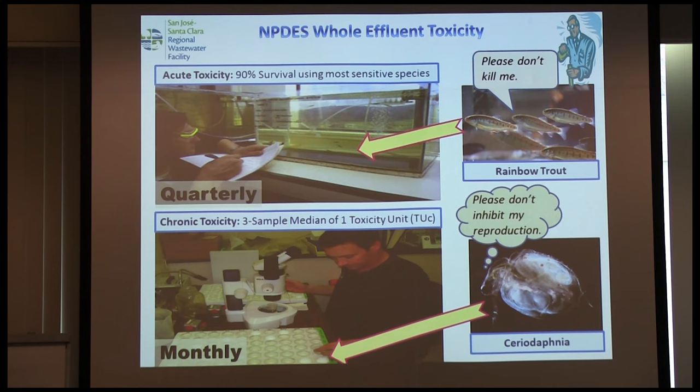The inspector often wants to go see the laboratory area where toxicity testing is done. We use a contract laboratory, bringing in larval rainbow trout — they have to be cultured. More often than not the lab is empty, but on the week of the test they bring in a shipment, put them in test tanks, controlling water, pH, and conductivity. Those fish swim in effluent for about five days, then you count the number that die — that's your acute test. Acutely toxic means: does your wastewater actually kill something?